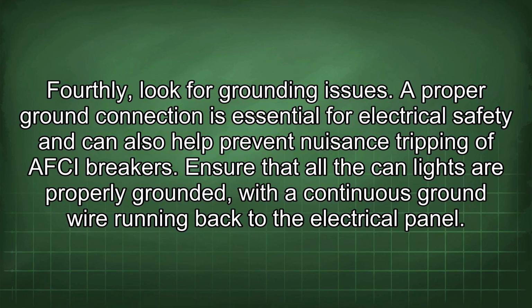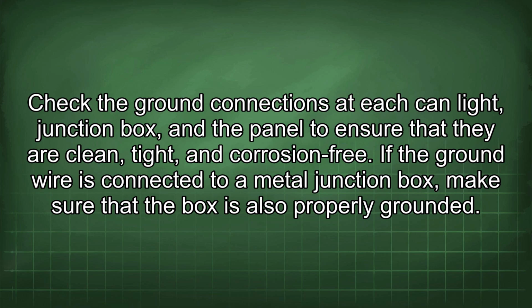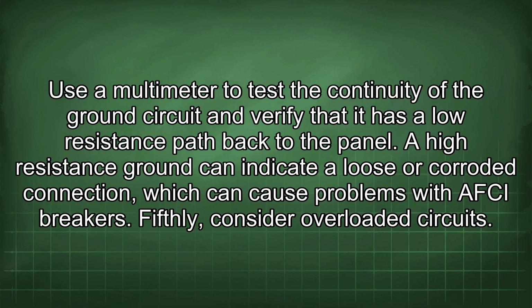A proper ground connection is essential for electrical safety and can also help prevent nuisance tripping of AFCI breakers. Ensure that all the CAN lights are properly grounded, with a continuous ground wire running back to the electrical panel. Check the ground connections at each can light junction box and the panel to ensure that they are clean, tight, and corrosion-free. If the ground wire is connected to a metal junction box, make sure that the box is also properly grounded. Use a multimeter to test the continuity of the ground circuit and verify that it has a low resistance path back to the panel.